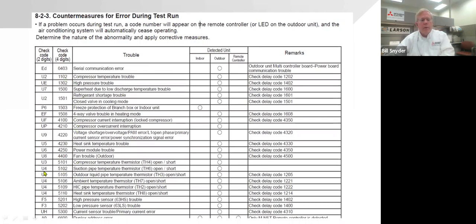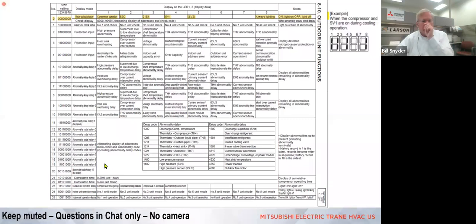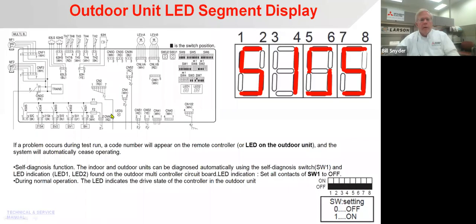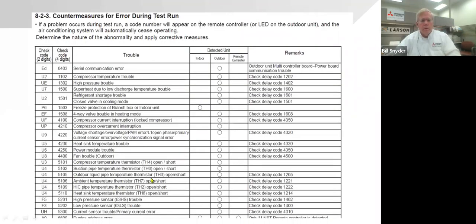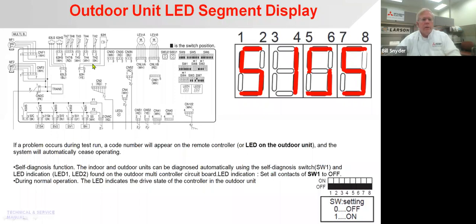If you had a thermostat or a controller on the inside, it would be sending this U4 code. And if you look up the U4 code, it's going to tell you it's the same as a 5105, and it's this thermistor. So it's telling you to check the thermistor. Now, let's go back one. These are the thermistors. And what did it say? TH3. So it's telling you to check TH3, which is this one right here, which is a white plug. It's telling you that that thermistor is probably bad.